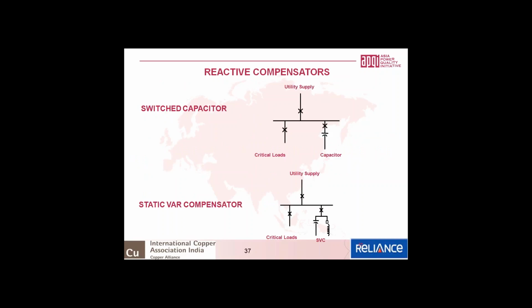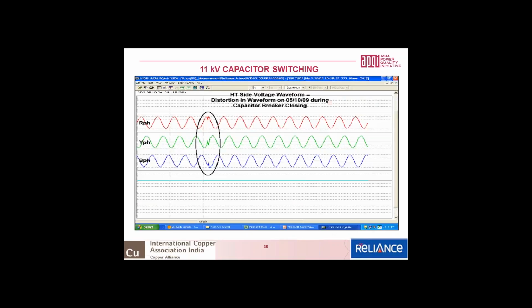The switched capacitor is the basic vanilla design, where conventional breakers are used to switch the capacitors on or off. The static var compensator is just a fixed capacitor in parallel with a thyristor controlled reactor. By controlling the current through the thyristor controlled reactor using thyristor firing, you can continuously change the power compensation. Of course, everything in life comes with a price.